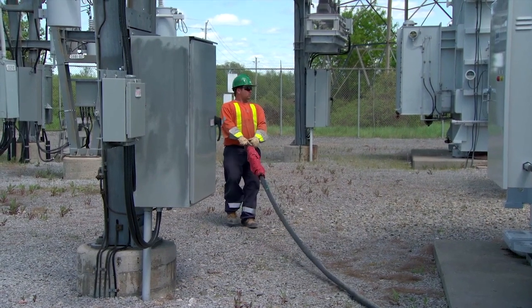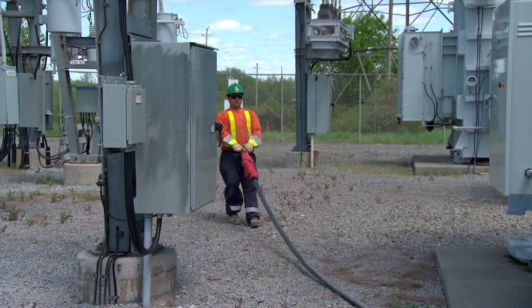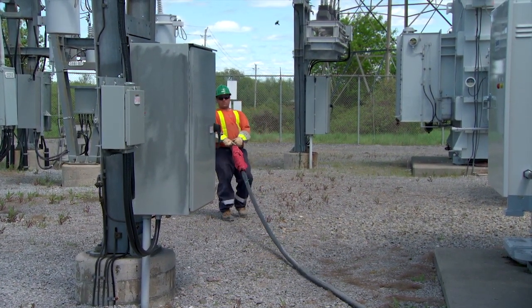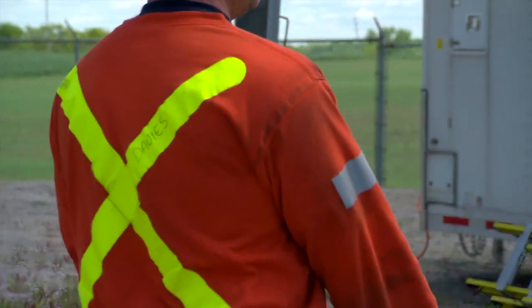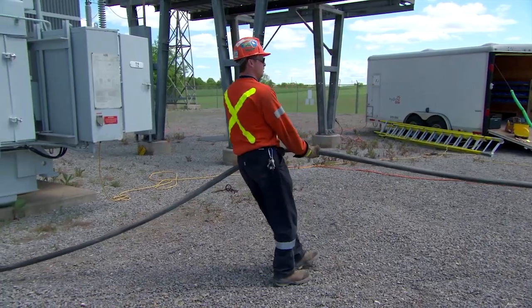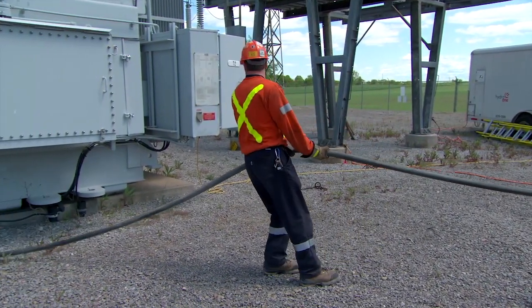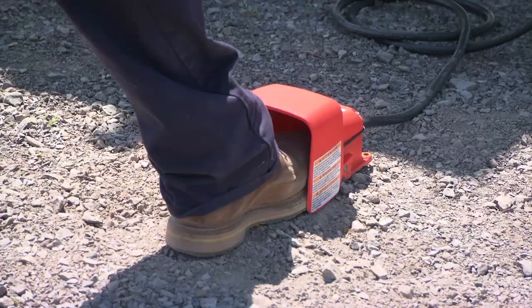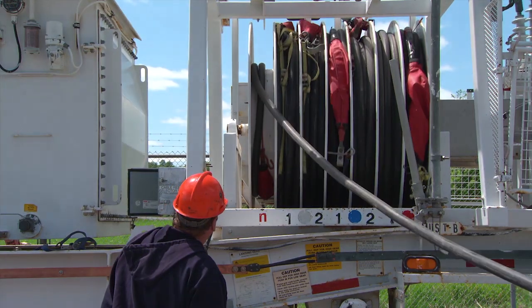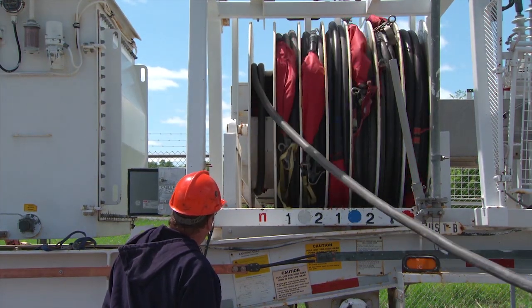cable. Lay out the low voltage cables in an orderly fashion and avoid overlap where possible. Make sure the phase markings match feeder and phase positions. Do not walk or step on the cables. The cable reel operator must pay close attention to the reel when unrolling the cables in order to avoid snagging or catching. He must also be prepared to stop the reel when the end of the cable appears.